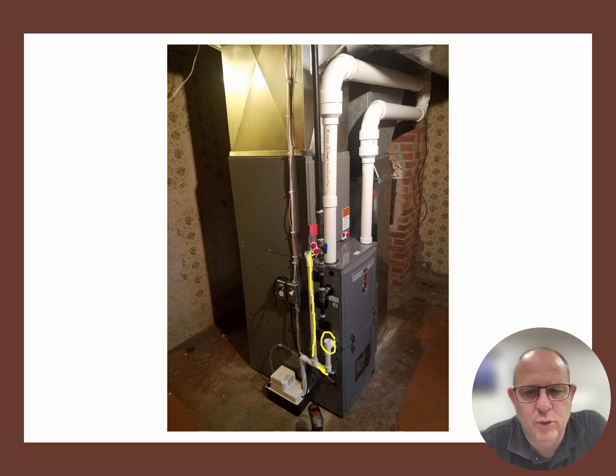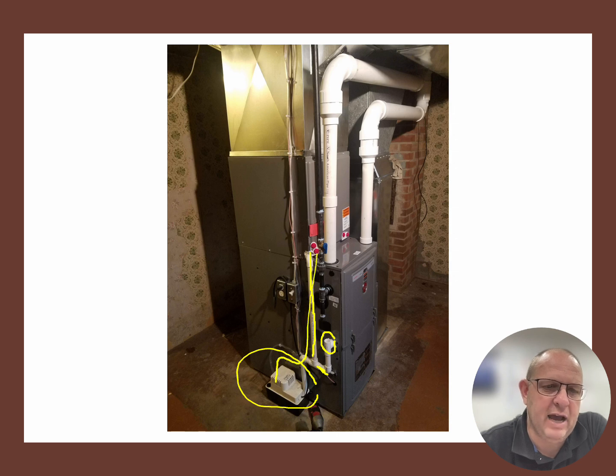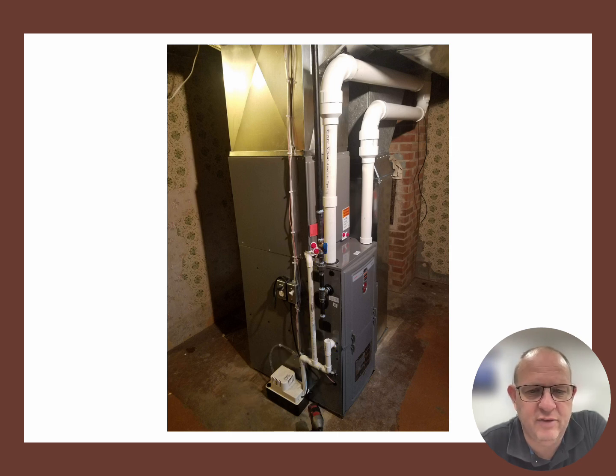Now these lines are going to come down to a condensate pump. We're going to take that and pump it up and out into a drain that we have a little further away from this furnace installation. Notice the ductwork is nice and straight, the wiring's nice and straight, with disconnect switches and switches for the pump. All of this was installed by me. Looking at the gas line, nice and straight coming down. A nice installation. Customers shouldn't have very many things to say about this, if anything was to go wrong with it.